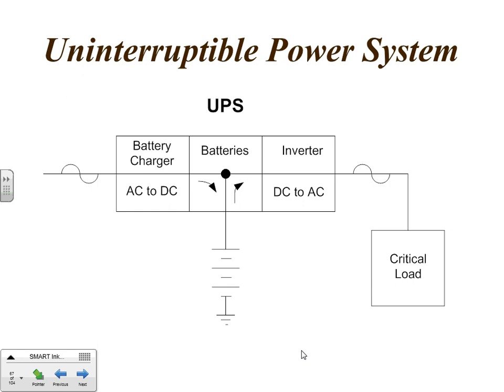I can't remember if I stole this or if I came up with this, but a UPS is basically made up of three parts. A battery charger, which changes AC to DC, charges the batteries, keeps them charged up. The batteries themselves, and then an inverter, which changes the DC back to AC and powers the critical load.